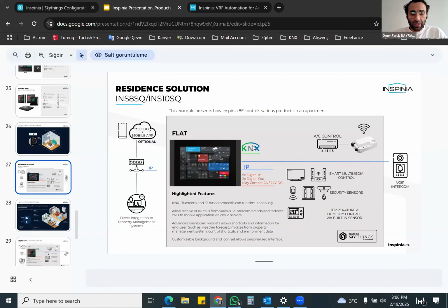It might be an IP network protocol and or bus solutions. Let's say KNX TP, KNX twisted pair communication. For this type of communication, like we said, you will need an additional add-on. We call it the KNX add-on, and you will put it in port 1 or 2. It doesn't matter. The KNX bus cable will come to the panel port, and after programming, the panel will control the system.